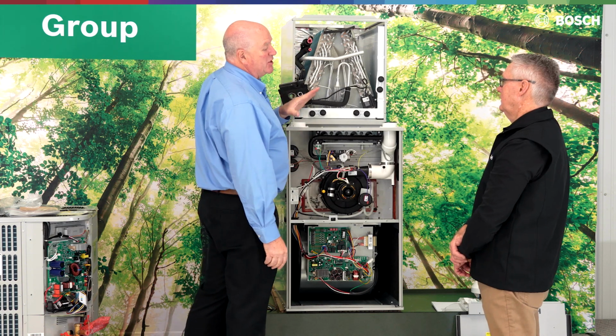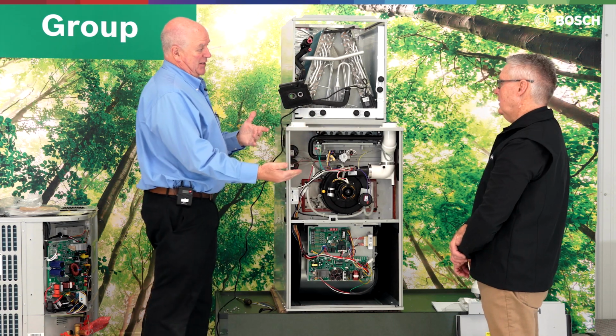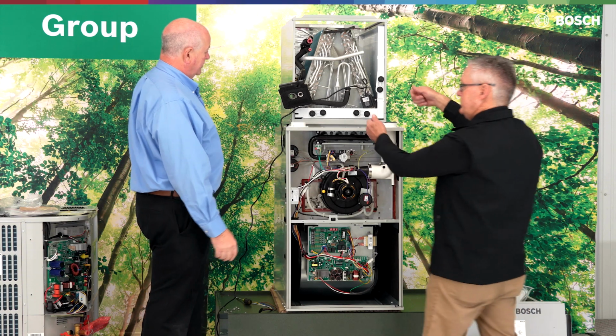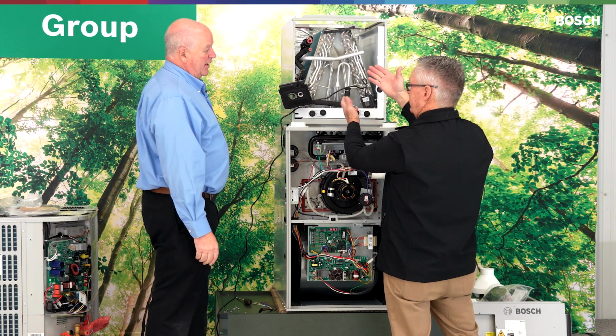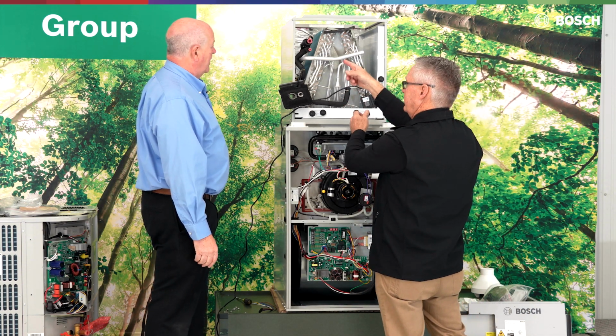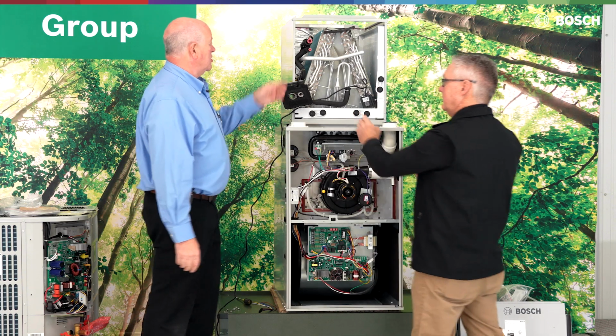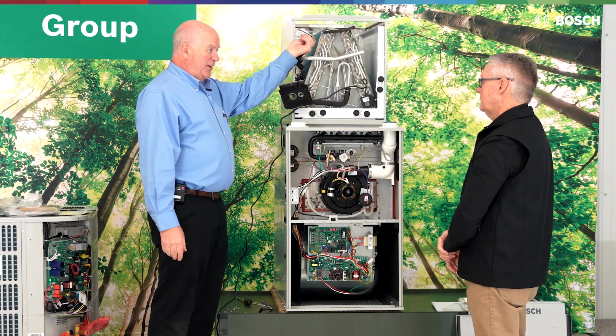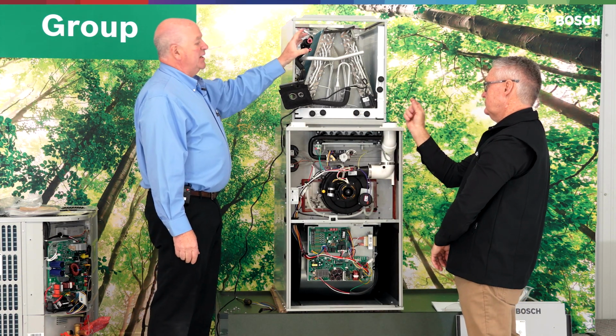And this is brazed in, as our manual says, braze. What happens if I have one of these machines that will automatically just mash a fitting into that? That's usually a problem because our swage doesn't allow that to fit. So I can braze a nipple on, and there you go, then do your process.